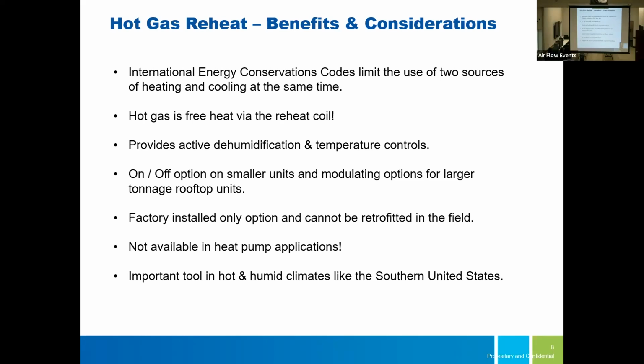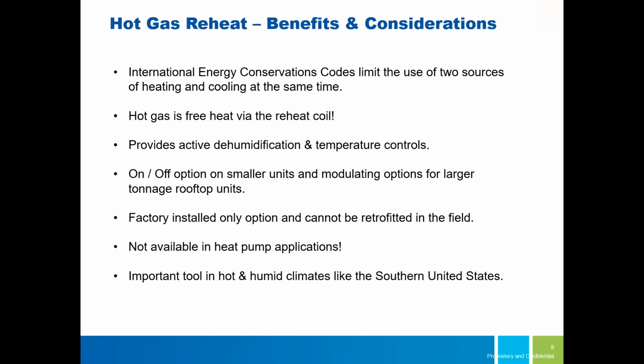When you say free, Kirby, you're taking that hot gas. Normally you'd be running that out to the condensing coil and running a fan to get rid of that heat. And now you're just using it sort of like a radiator, but inside your building instead of outside the building. That is a great analogy, and I never really thought about it like that. But yeah, otherwise that hot gas is going to go out to the condenser and get rejected, right? So if it's going to be rejected, you might as well use it, right?